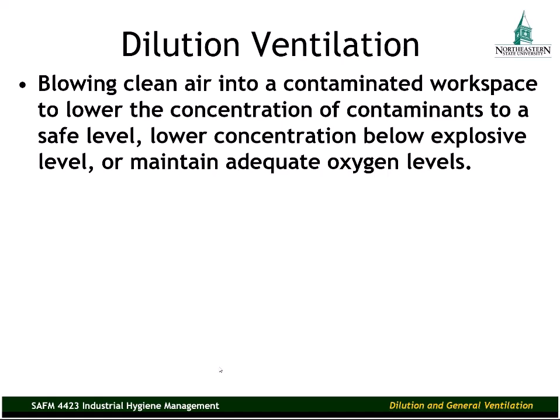Another big reason for dilution ventilation is just to maintain the adequate oxygen level in the space. And you've heard me mention it 20 times. In my experience, that's the biggest problem in a lot of confined spaces. Not enough oxygen in the space to support life. So as we go through this topic, we're going to talk about all of these different variations on dilution ventilation.